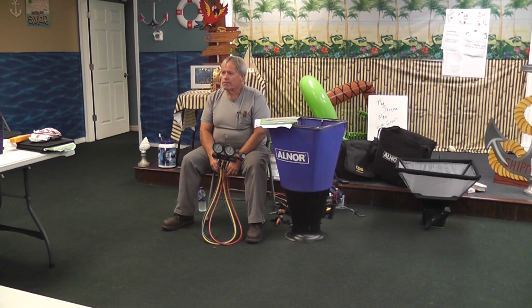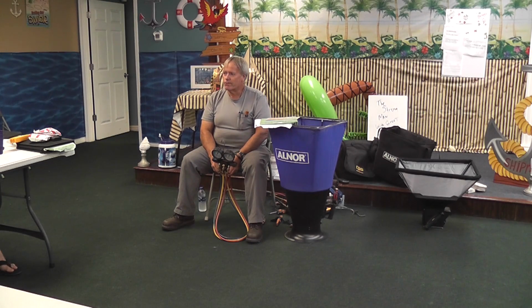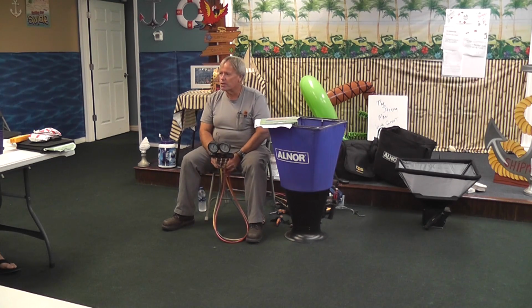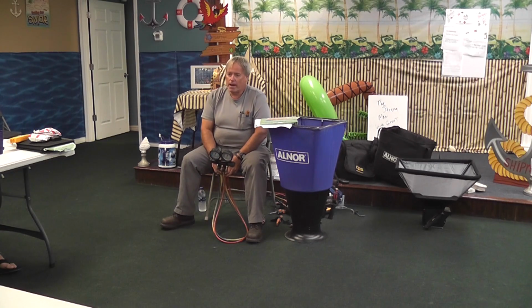They hook gauges to it, and oh wow, look, the gauge says I'm right at the pressure I'm supposed to be. Doesn't mean you have the right amount of refrigerant, you're just in that window of area that's going to give you those pressures. Temperature of the refrigerant lines didn't matter to them, apparently. There was another way to charge these machines, it's called by approach, and it would have worked if the coils were clean. They weren't. I took out 45 pounds of refrigerant from one machine. I worked on 6 machines. By the time I got done, I used up what I recovered, and I still didn't have enough gas to fill the last circuit up. Temperature was right, but now I have control of the humidity and it dries the store out.